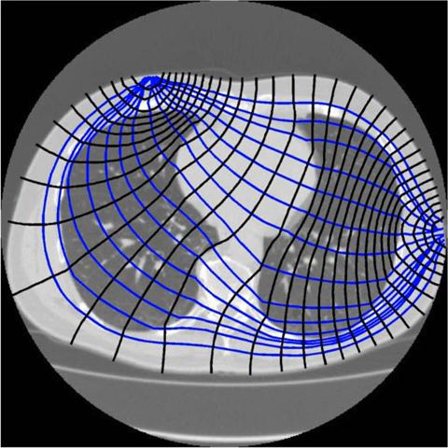Time difference EIT bypasses most of these issues by recording measurements in the same individual between two or more physiological states associated with linear conductivity changes. One of the best examples for this approach is lung tissue during breathing due to linear conductivity changes between inspiration and expiration which are caused by varying contents of insulating air during each breath cycle. This permits digital subtraction of recorded measurements obtained during the breath cycle and results in functional images of lung ventilation. One major advantage is that relative changes of conductivity remain comparable between measurements even if one of the recording electrodes is less conductive than the others, thereby reducing most artifacts and image distortions.